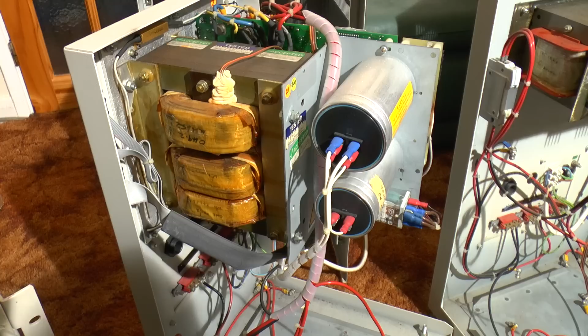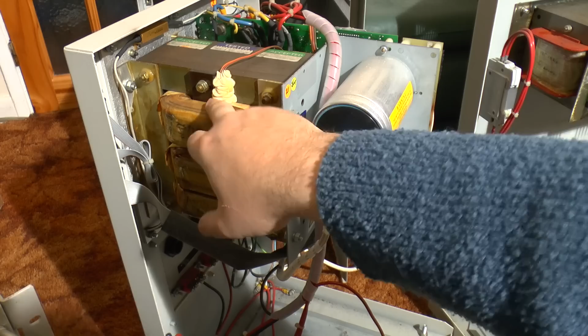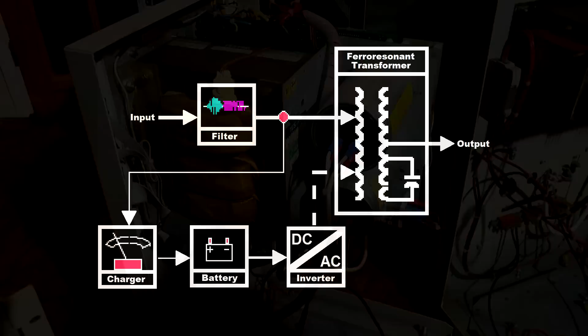battery breakers. Now this is a ferro-resonant UPS, hence the rather strange and rather hefty transformer. And oddly enough in here as well we've got these two capacitors, which are rated 22 microfarad at a whopping 930 volts. This transformer, I've counted at least 20 terminals between the top and down the side and up the bottom as well. There's a lot of connectivity on this thing. It's a really strange way of working, but I'll post a diagram here which I found on the internet showing the rough operation of a ferro-resonant UPS.